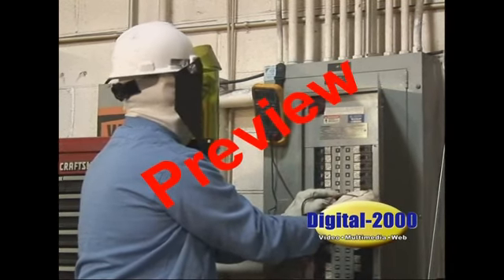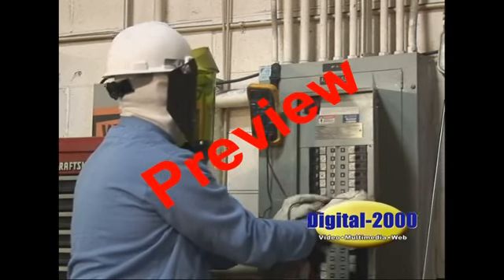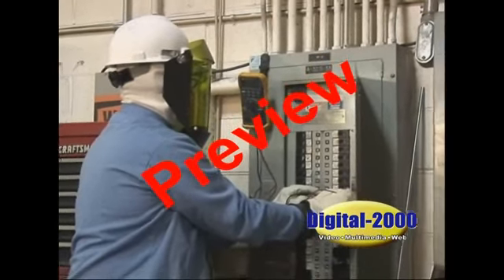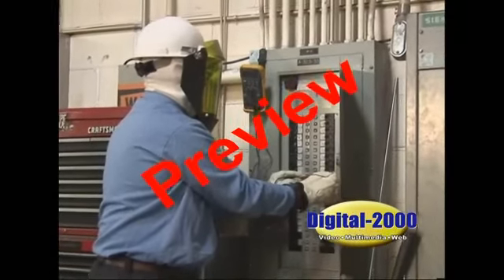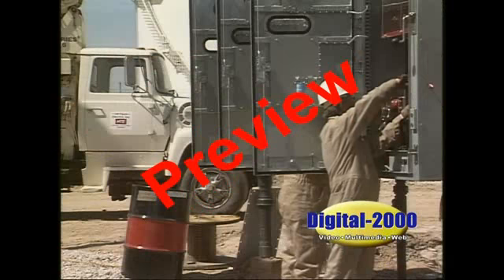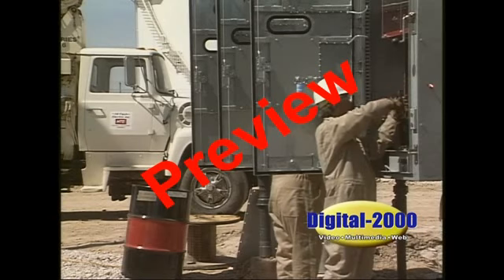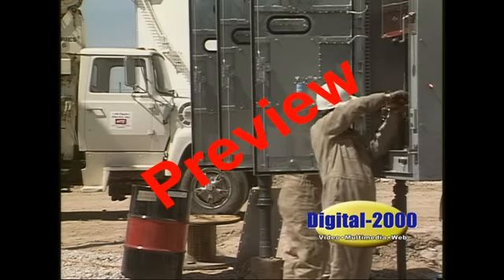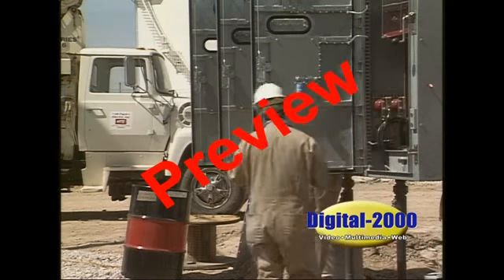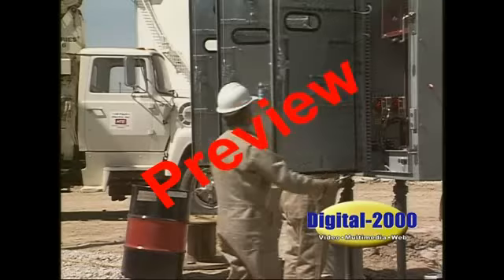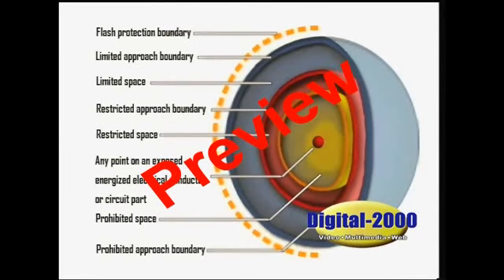A worker entering the flash protection boundary must be qualified and must be wearing appropriate personal protective equipment. When we say appropriate PPE, that means special arc flash PPE and clothing. In an actual situation, before a worker is permitted to approach equipment with exposed live parts, these arc flash boundaries must be determined and proper level of PPE established for the particular boundary. These boundaries must be calculated by determining the incident energy. We're not going to discuss how the boundary is determined, as it is a highly technical process and will be performed generally by electrical engineers. There is also numerous software available for developing these arc flash assessments.